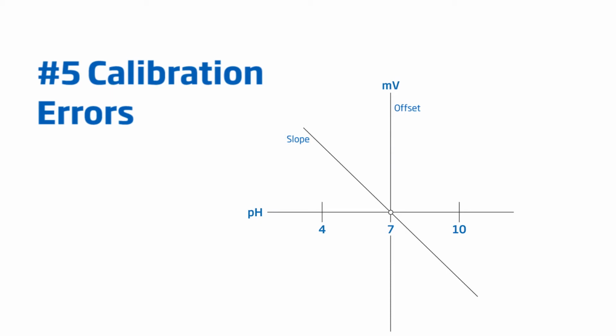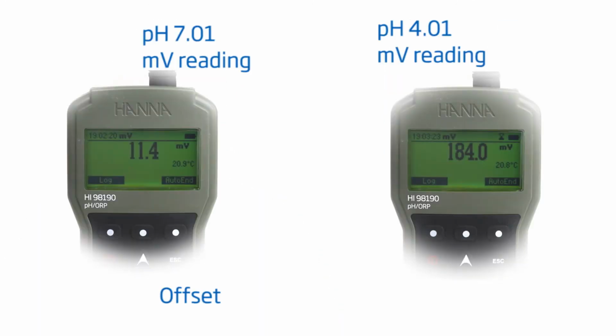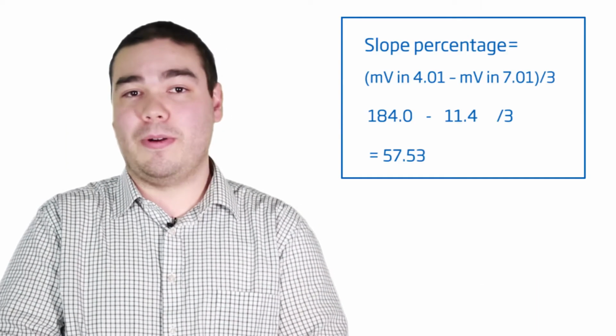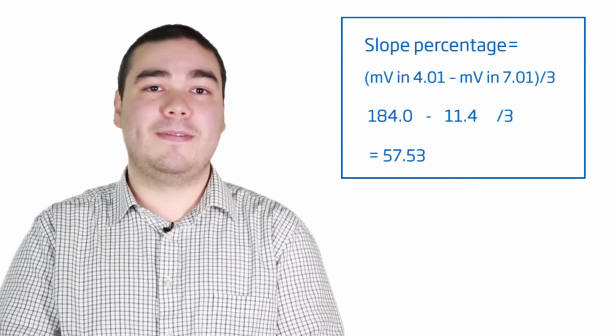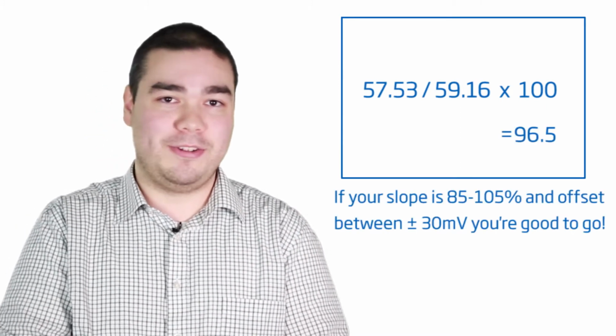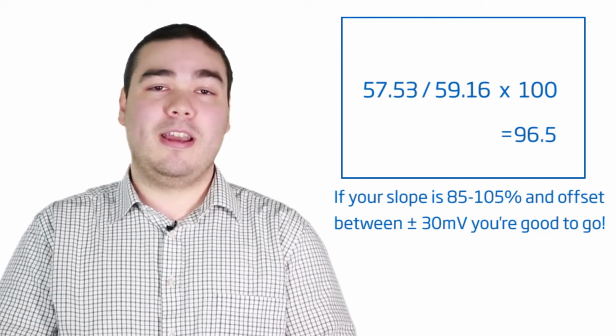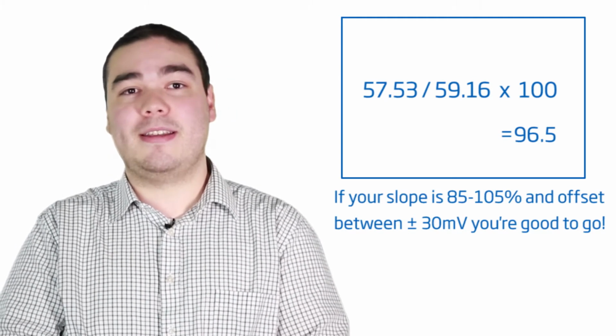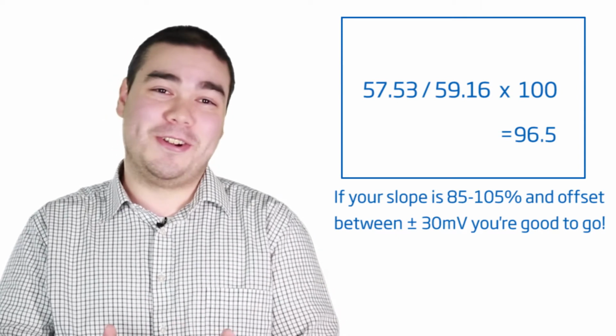We're now at the halfway point. pH mistake number 5, calibration errors. If you're worried about the condition of your electrode, you can always check the electrode slope and offset. To do this, you need a meter that reads millivolts and pH 4.01 and 7.01 buffers. The millivolt reading of your pH 7.01 buffer is your offset. To check your slope, take the millivolt reading of your pH 4.01 buffer, subtract your offset reading, and divide by 3. Divide that answer by 59.16 and multiply by 100. This is your slope percentage. If your slope is 85 to 105% and the offset is plus or minus 30 millivolts, you're good to go.